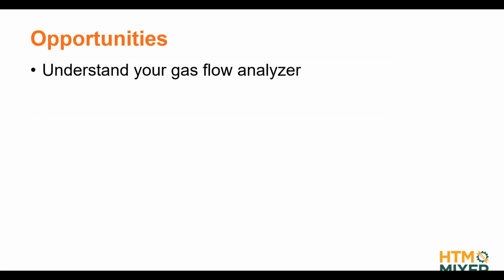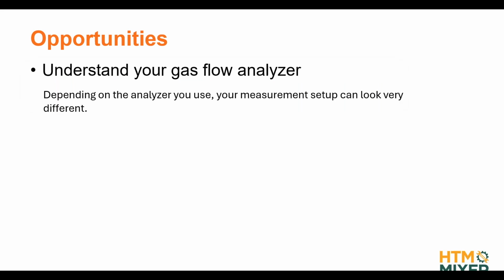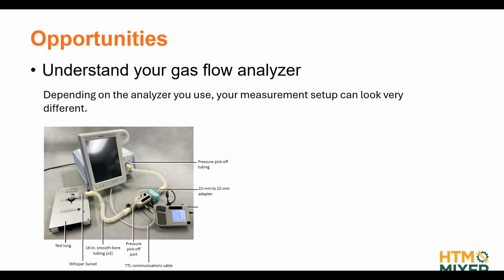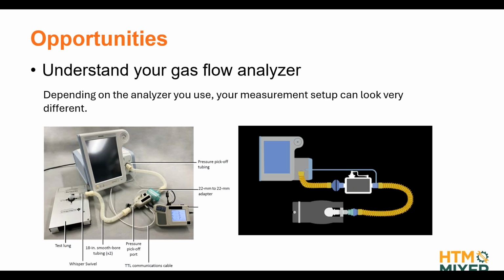There are many different models out there, so you need to understand what is being measured and how the parameters are being measured, and then very often you have setup information also in the user manuals of these gas flow analyzers, because depending on the analyzer you use, the setup we've seen earlier in this picture could look like this for a different analyzer, right? So some analyzers have a lot of different components, some analyzers have very few of them. So it's important that you understand what your flow analyzer is measuring inside the main flow channel and what needs to be measured with additional modules.